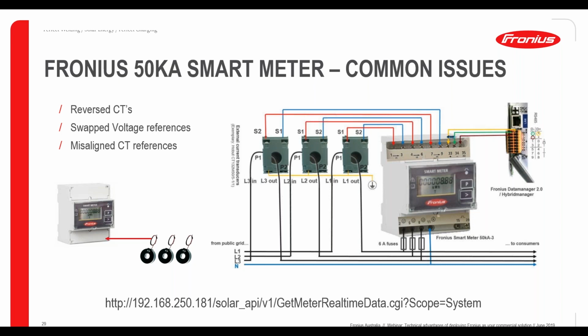Another typical issue that we see here is a misaligned CT with voltage reference. For example, the red CT is connected with the blue voltage reference. It's a bit harder to troubleshoot, but we'll give you a few tips on how. There's a link at the bottom here. If you use this link, bear in mind the IP address needs to be the IP of the Fronius user interface of the master inverter. If you use this request in your browser, you'll get a response which will look something like this.